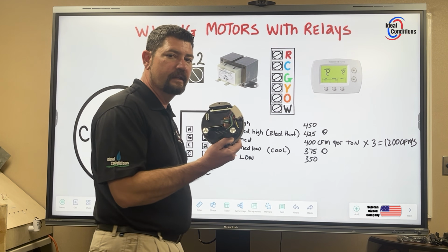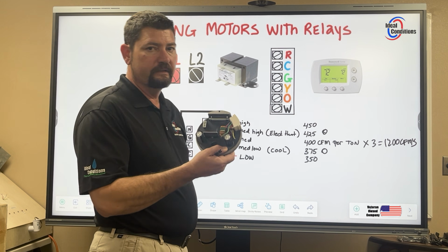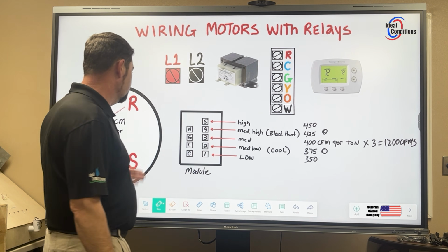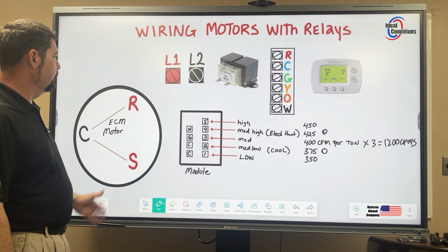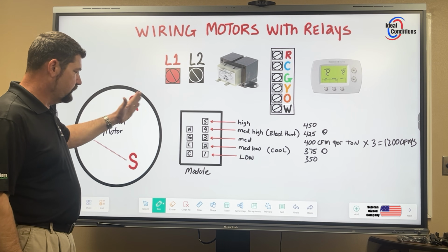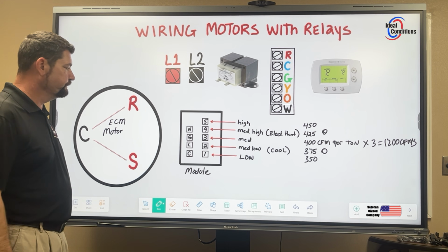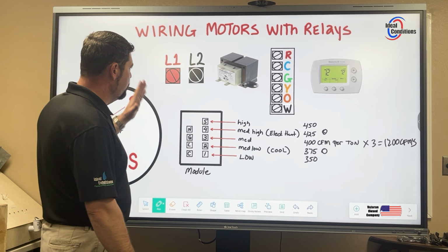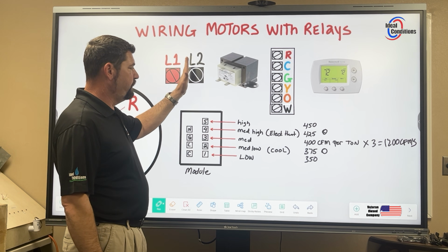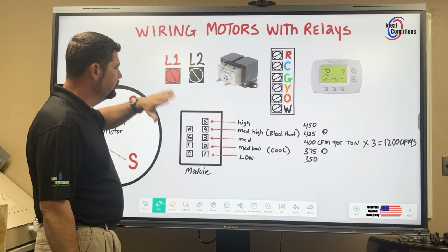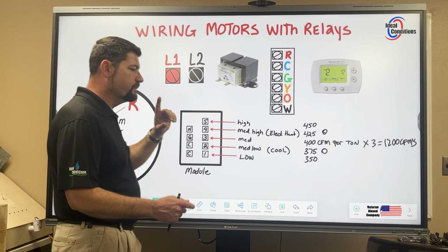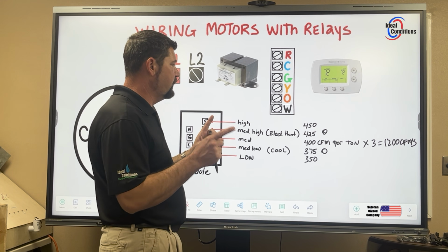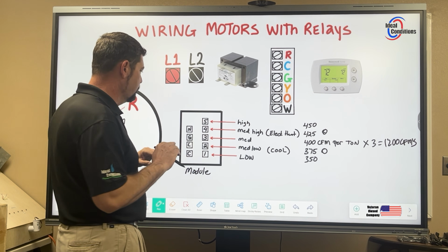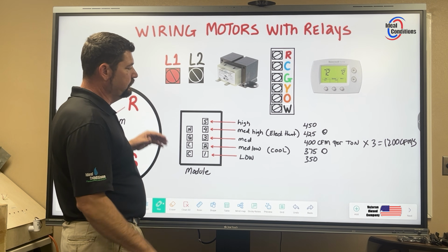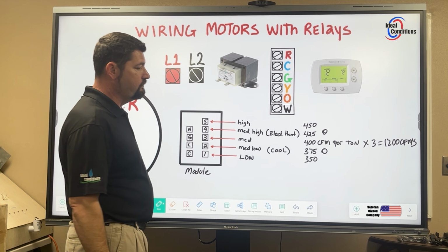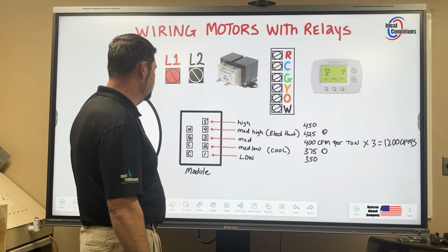You can clearly see that a leg of power is going to tie into these capacitors and provide that 3rd leg for my motor to have a start winding. So what we're going to do is make it very interesting here, just to know that run and start are going to be on the same leg. Okay. When we wire this up, you want to wire 1 leg of power all the way through. When that leg of power is done, you want to go to the 2nd leg of power. This way we're observing both ends of the wires to make sure that we're not crossing paths of electricity, causing harm to yourself, most importantly, and then secondly, adding more work to your plate because you've created more damage to the equipment.